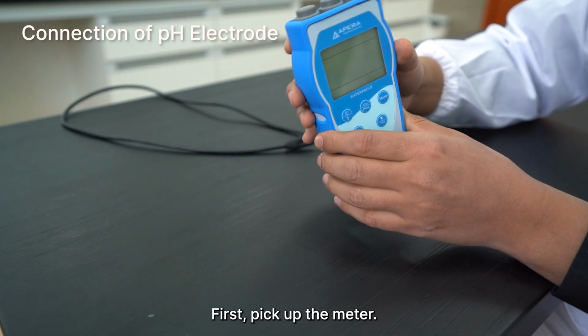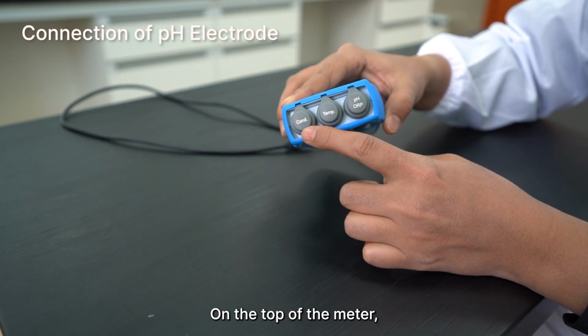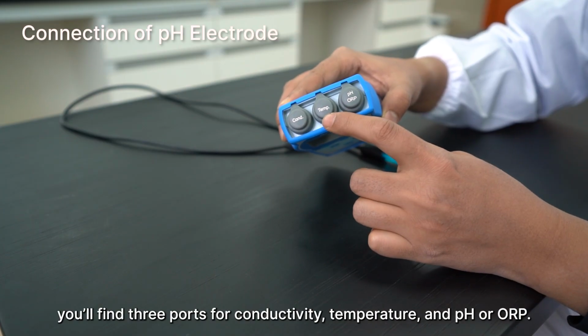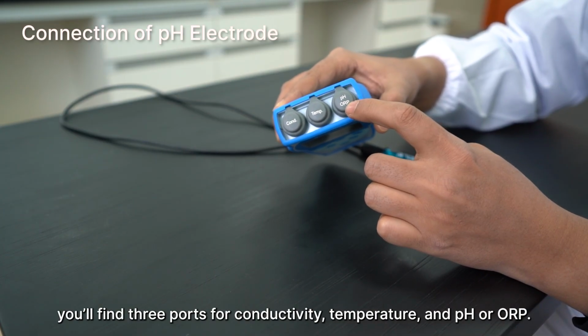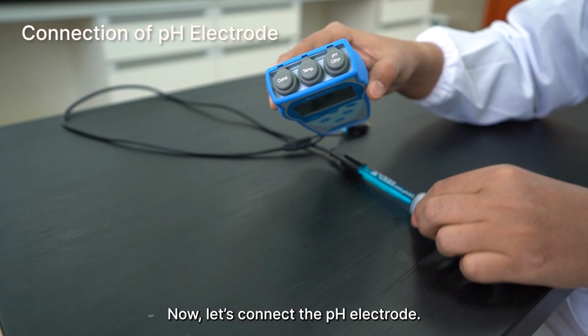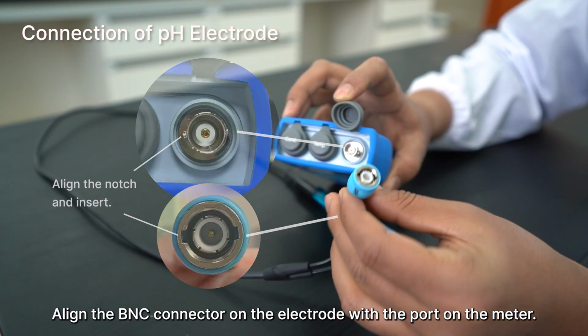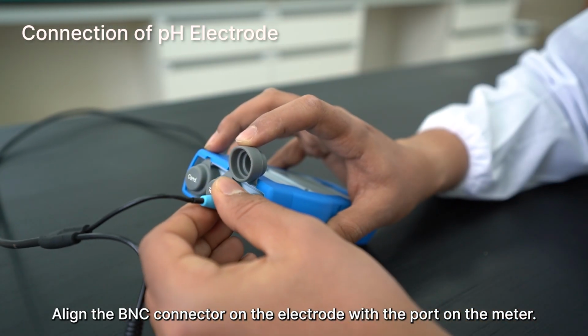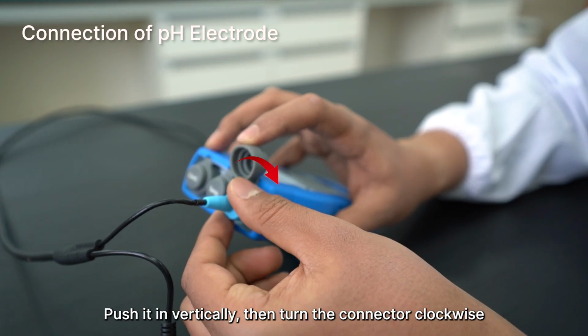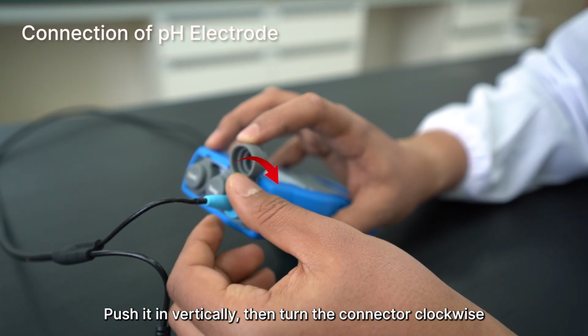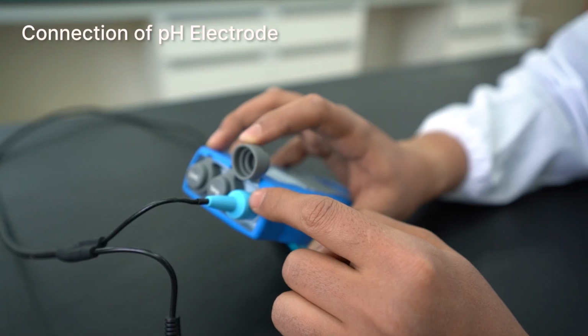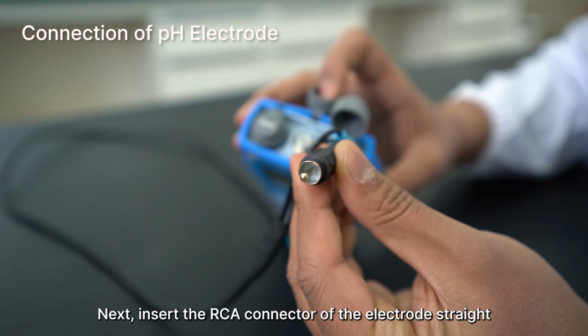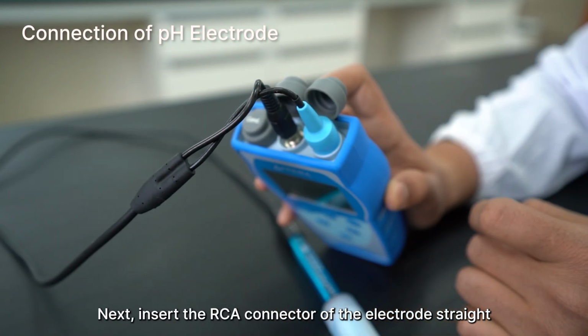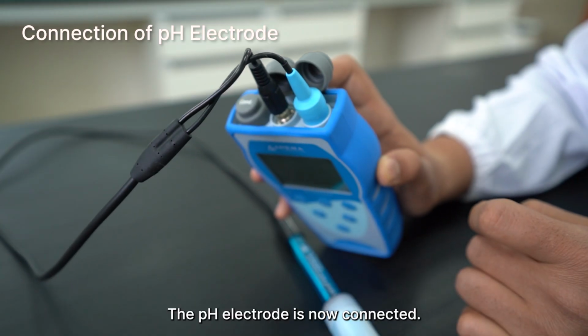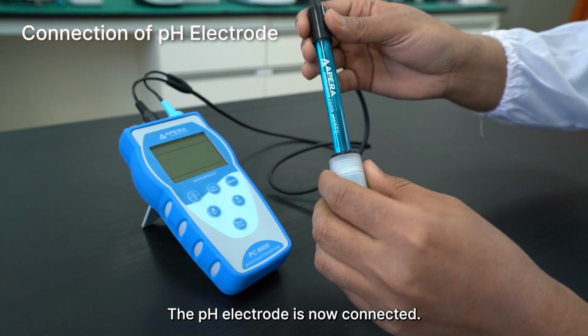Connection of pH electrode. First, pick up the meter. On the top of the meter, you'll find 3 ports for conductivity, temperature, and pH or ORP. Now, let's connect the pH electrode. Align the BNC connector on the electrode with the port on the meter. Push it in vertically, then turn the connector clockwise until you hear a click. Next, insert the RCA connector of the electrode straight into the temperature port. The pH electrode is now connected.